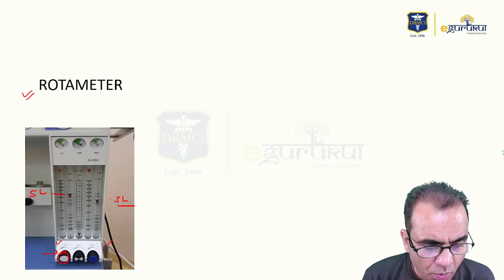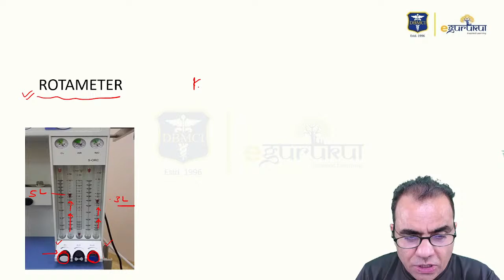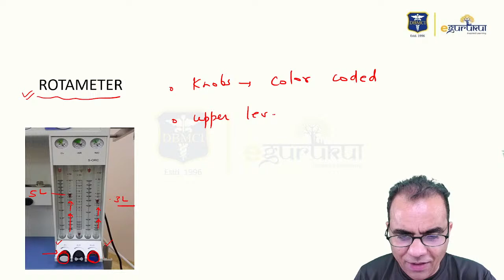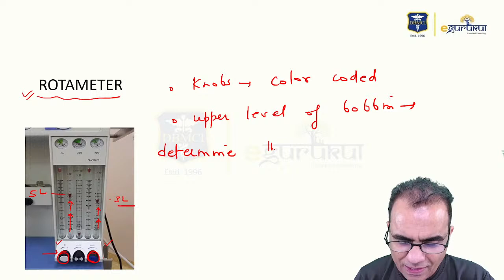So, the important thing about the rotameter is that the flow control knobs are color coded, and secondly, it is the upper level of the bobbin which determines the flow rates. I'm telling this because they have asked this question once or twice: whether it is the upper level, mid level, lower level. It is the upper level of the bobbin which determines the flow rates, and the flow control knobs are also color coded. Of course it will be white for oxygen, black for air, and blue for nitrous oxide.